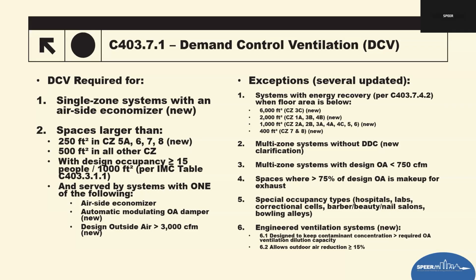So one of the biggest changes is that any single zone system with a required economizer must now include a DCV. So this is new and expands the DCV to many rooftop units in commercial buildings. And I should have said this in the beginning, but this is what the code book is written and how it's published. This is not a final version of either a Texas approved, amended, and adopted code or a jurisdictional approved code. So this will all be up to cities, jurisdictions, and code officials to determine whether these things are required, but this is what the code book states.